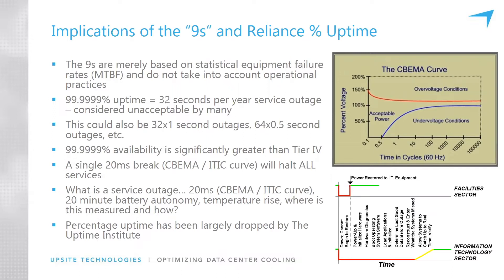If you think about six nines availability — that's 99.9999% uptime — that still allows for 32 seconds a year of service outage. That could be a single 32-second period, or 32 one-second outages, or 64 half-second outages, each of which is actually going to take out the entire IT load if that outage is on the electrical side.